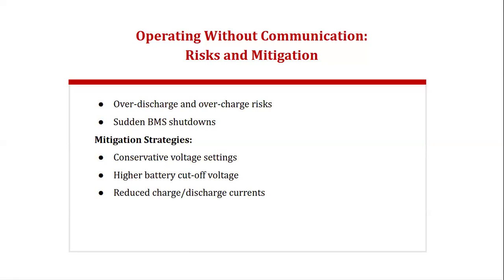Then reduce charge and discharge current. You can do that on some inverters, where you can set the maximum load. This is also applicable to a general situation for all the batteries. If you know that the current of the battery cannot withstand the load, then you have to strategically put things in place. You set on the inverter, if the inverter has that function, that you must not be able to load it beyond this power. When you want to do that, the inverter will tell you overload and probably shut down. Or you put external devices that you have set to help you do that.